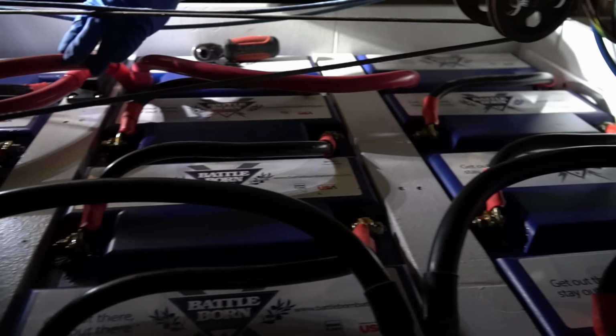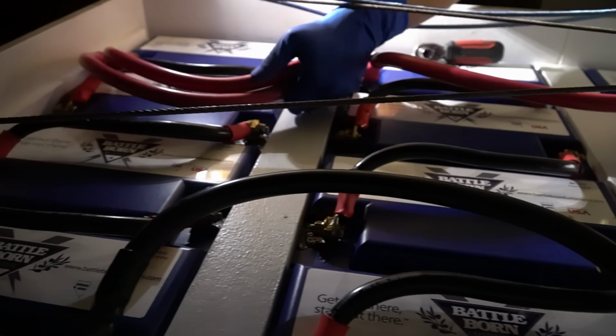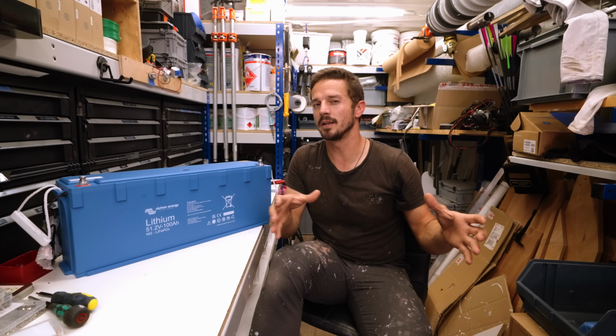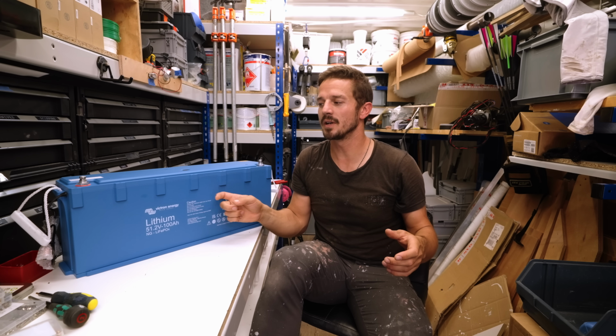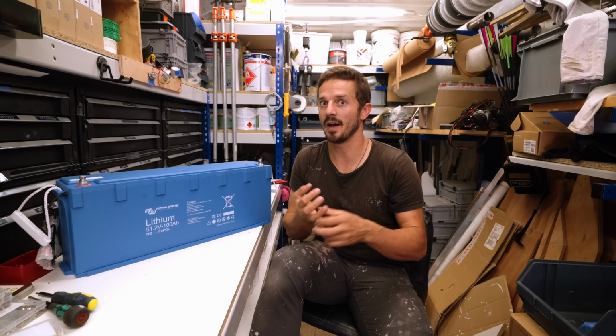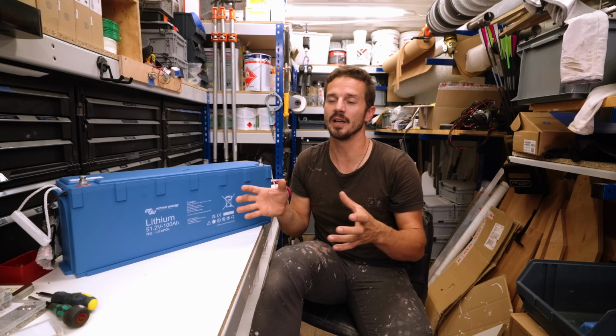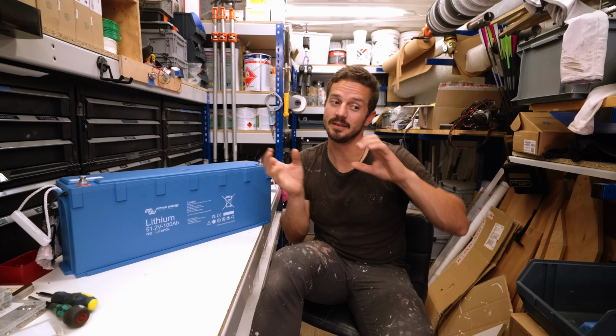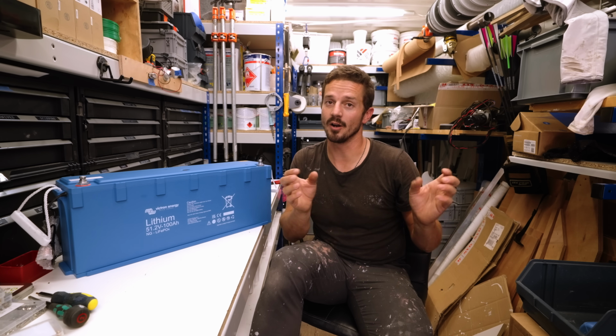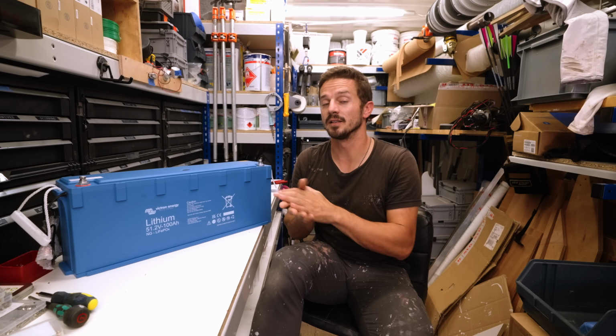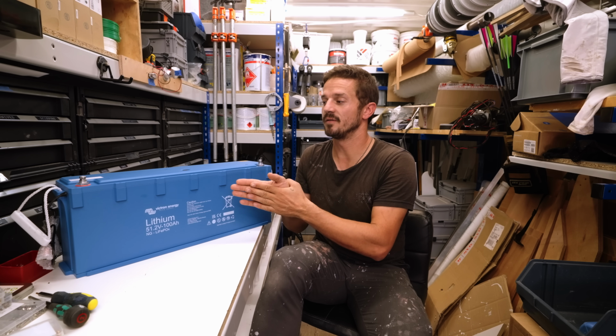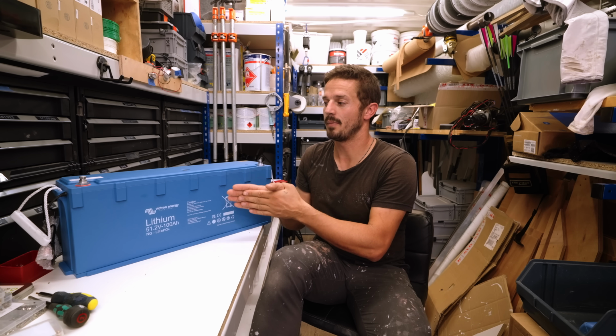What we had before was our batteries wired in series and parallel, so the whole bank just had 1 fuse. But because these are higher capacity, higher voltage, their ability to dump a lot of current all at once in a fault is much higher. So we need to fuse each individual battery.